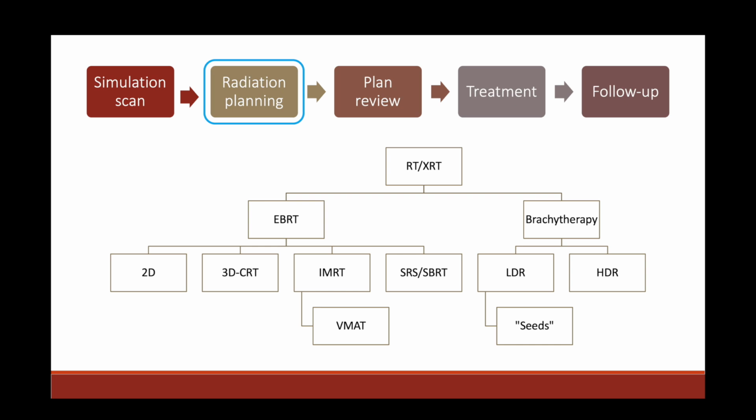High dose rate brachytherapy is usually delivered using an iridium-192 source, which is a higher energy radioactive seed. Typically this is used for treating things like gynecologic cancer. It can also be used to treat prostate cancer. But because this is higher energy, it's not at all safe to permanently implant it into the patient. So we deliver that type of radiation using a machine known as an afterloader that is connected to a catheter inserted inside of the patient, and it delivers the seed for a brief period of time, and then that seed is extracted.